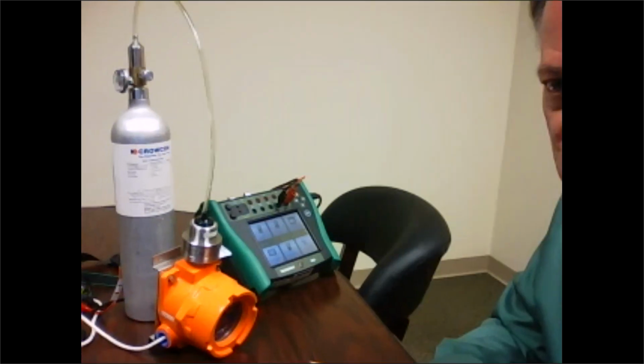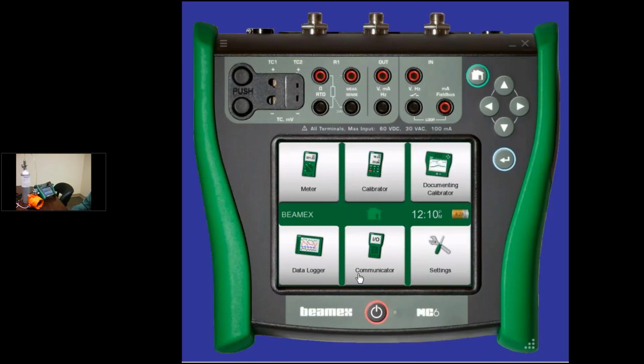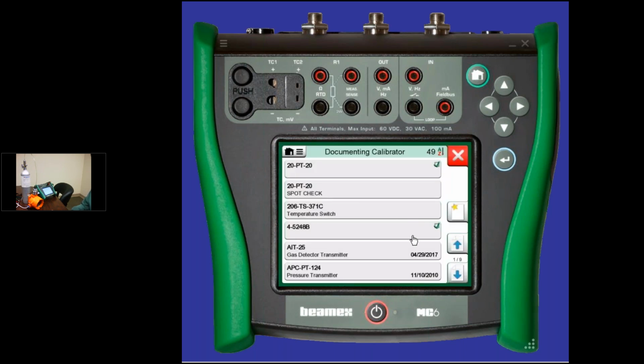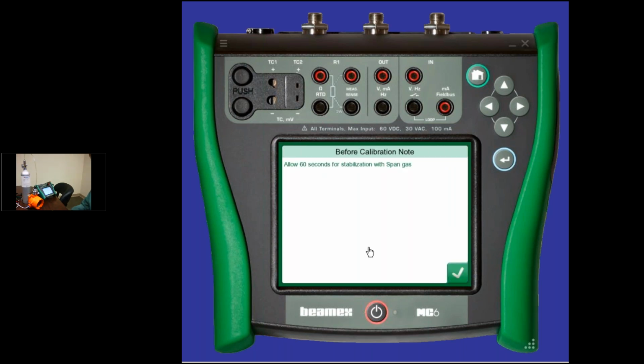See, I've shown you my screen. I messed up here. Let me show the MC6 controller. And I'm not going to call it my software, but you saw Roy downloaded to the calibrator. So I'm just going to jump right into documenting calibrator here. And so when I click on this, I have a lot of instruments in my MC6, but here's AIT25, my gas detector transmitter. So that's what's on the table here. So I tap that folder. Here's a little reminder message. It's reminding me that I should wait at least 60 seconds for stabilization when I'm exposing the sensor to span gas.